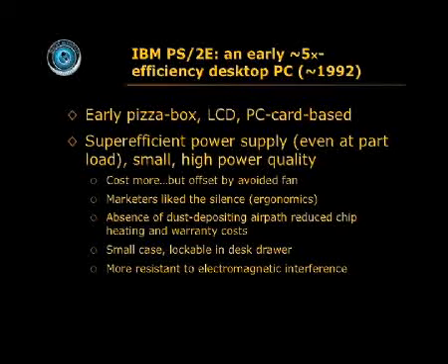It had PCMCIA architecture. It was the first pizza box form factor. And with much argument, they were persuaded at IBM to use a very efficient power supply. Normally they use these absolutely dreadful switching power supplies that might be 60 or 70% efficient at full load, but they get dreadful at part load, which is where they spend most of their time. And instead we found a mid-90s% efficient Swedish one the size of a pack of cigarettes that gave terrific power quality and had quite flat efficiency across the load curve.